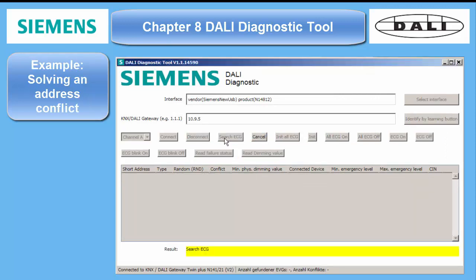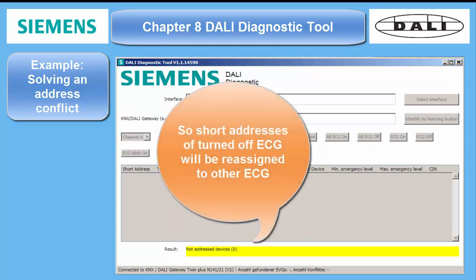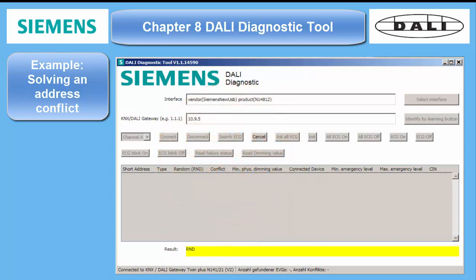Example: solving an address conflict. The automatic addressing algorithm in the DALI Live tool in ETS can only handle hardware which is entirely powered. First it scans the bus for all ECGs which are online. Non-ambiguous ones will be left unchanged. Those bearing ambiguous short addresses will be initialized — meaning the short address will be erased and set to 255, and the long address will be randomized once more. Then these initialized ECGs will be assigned new short addresses in ascending order.